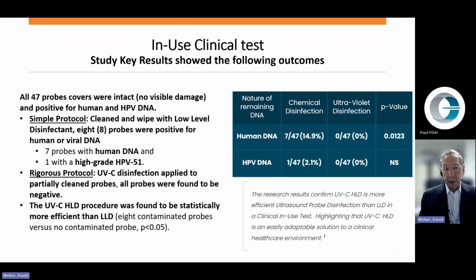In the upper right, you can see a chart that demonstrates these numbers. Again, human DNA, chemical disinfection, positive 7 out of 47, approximately 15%. Ultraviolet disinfection is 0 over 47, 0%. HPV DNA found in 1 over 47, 2.1% with chemical disinfection, found in 0 over 47 with ultraviolet disinfection, 0%. This research confirmed that UVC high-level disinfection is more efficient for ultrasound probe disinfection than low-level disinfection in a clinical use test, highlighting that UVC high-level disinfection is an easily adaptable solution to a clinical healthcare environment.